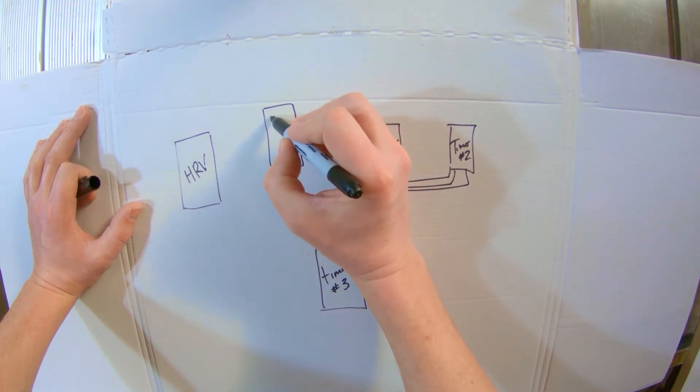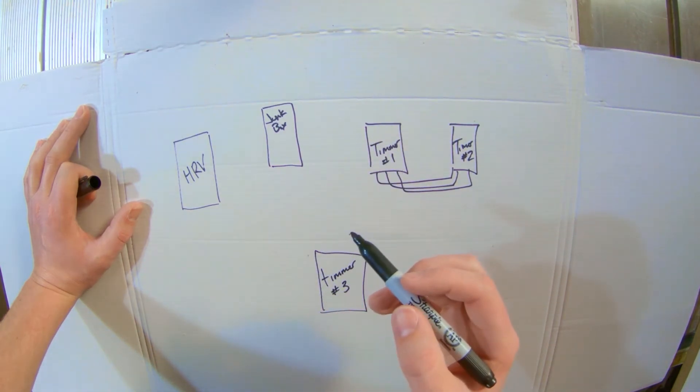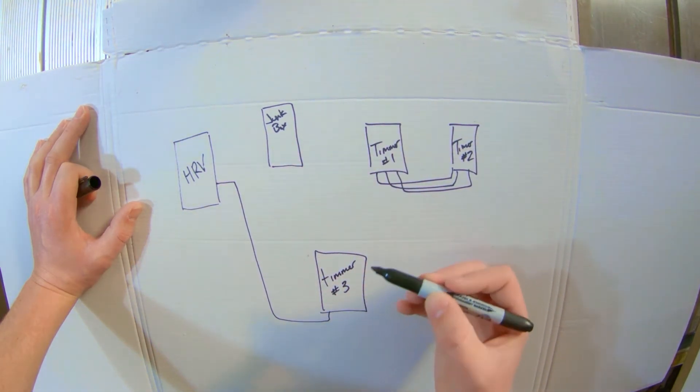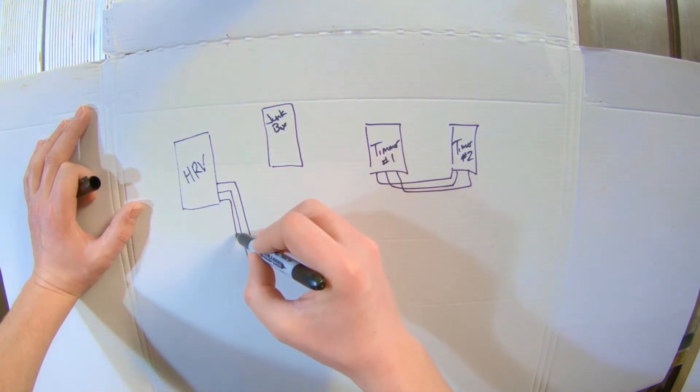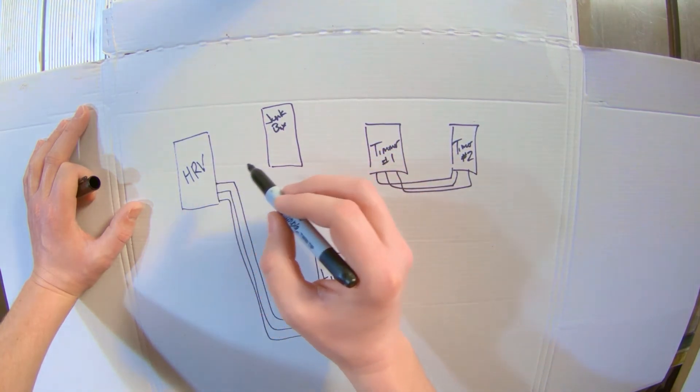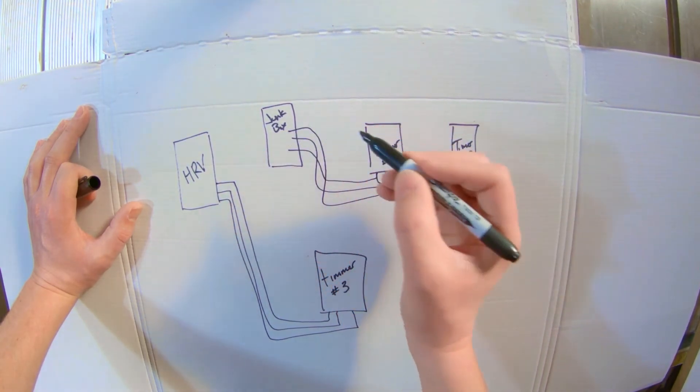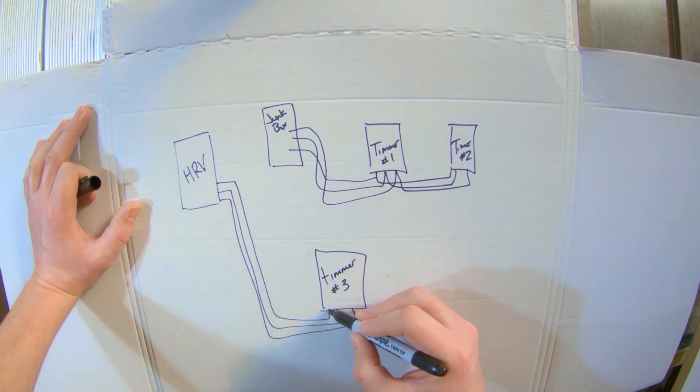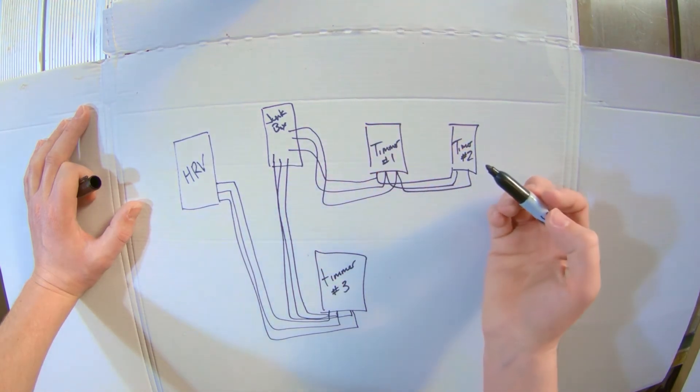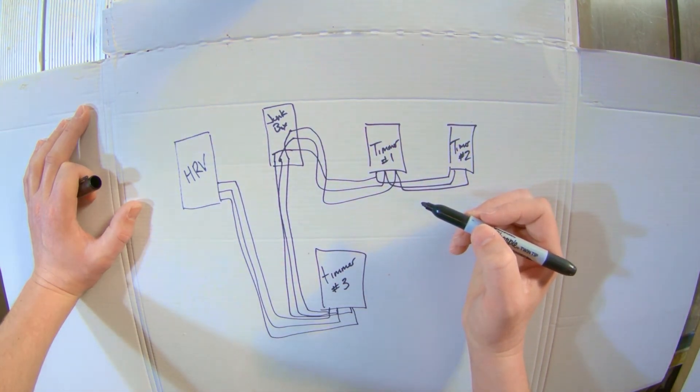What we'd do is you'd put a junction box in your mechanical room, just surface mounted so you got access to it. And what you do is you'd run a new cable from your HRV into your timer three. This is your new timer. You'd take your cables that were running from timer one to the HRV and you'd put them into the junction box. So you got these cables now running this way. And then you run a second cable from your timer to your junction box. And then you tie these together. Just pigtail them and you'll be good to go.